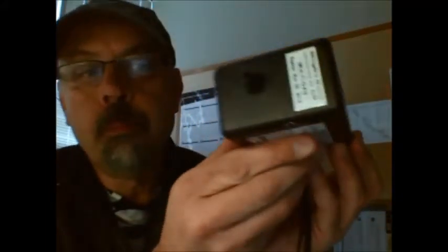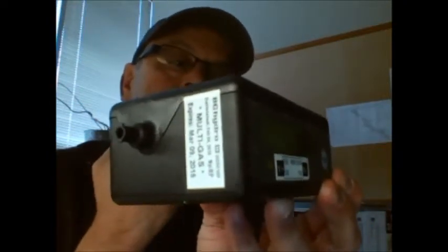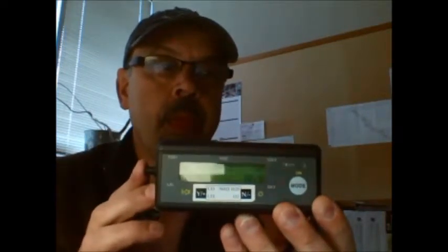Now that we've done that, we are going to proceed, and we're going to check the sample pump. Now you can hear the sample pump running, but that doesn't necessarily mean that it's drawing in a sample. So what we do is we plug the input to the detector, and that's what we get. That means that we plugged off the sample flow and the alarm comes up. So we push the yes button again and it goes back on. Now if that alarm did not come up when we did that, that means there's something wrong. There's a leak, or the pump is not doing its job. So you would not use that gas detector. You would go grab another one, and you'd bring this into the instrument shop, and they would go over it.